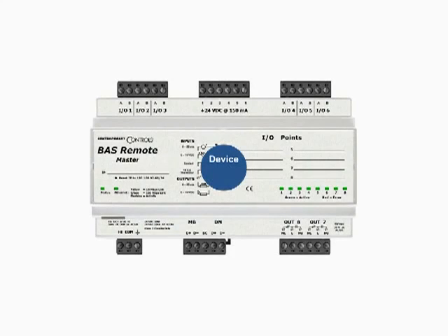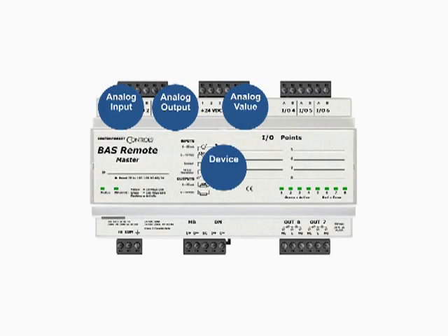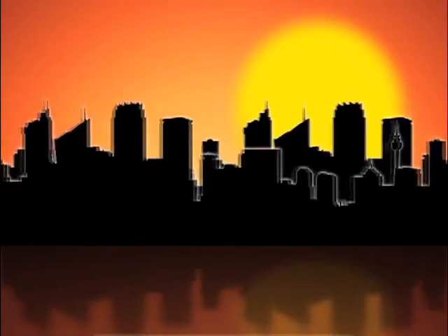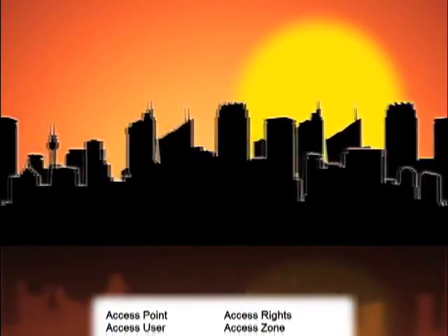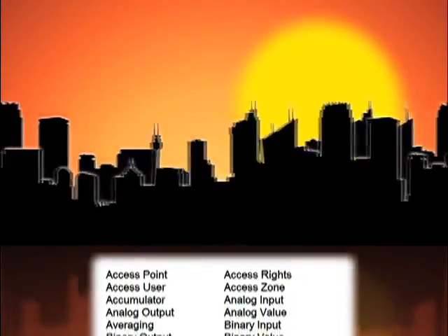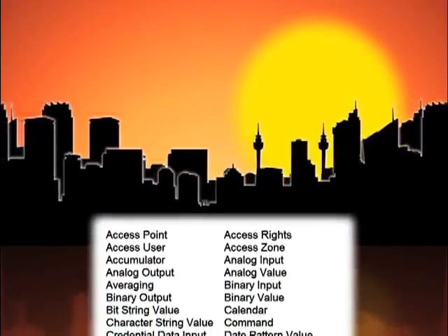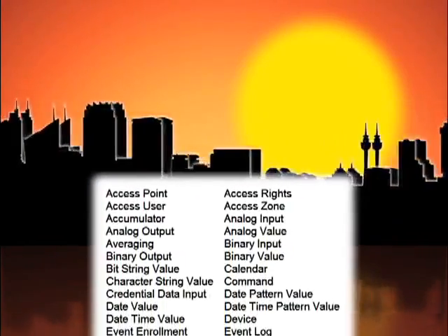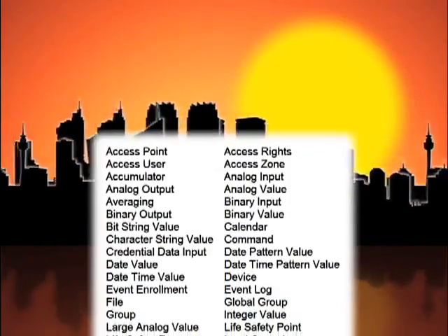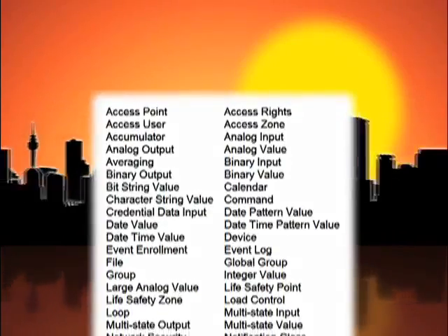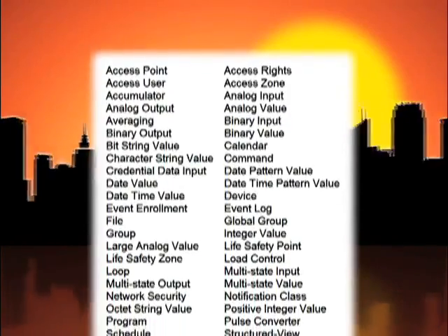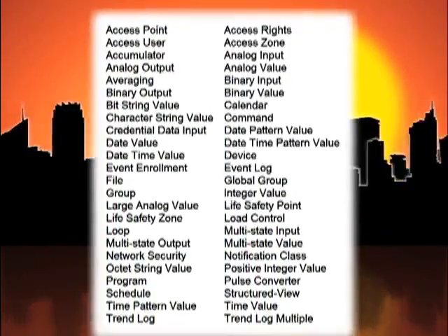With device modeling, a physical BACnet device appears as a collection of objects with properties that represent data and functionality. These objects can belong to different object types. Objects represent either physical or virtual information such as analog and digital inputs and outputs, control algorithms, specific applications, and calculations. There are currently 50 predefined BACnet objects, and the number continues to grow as additional needs are recognized.